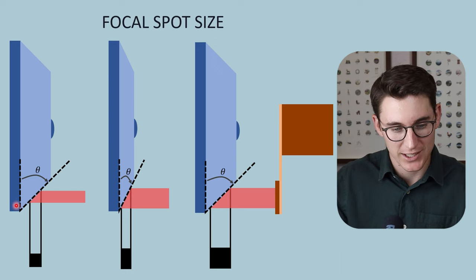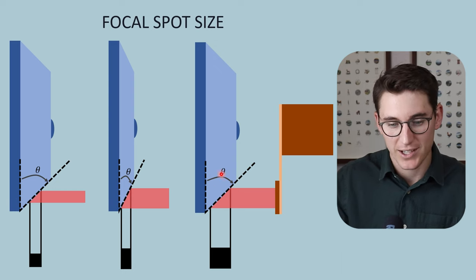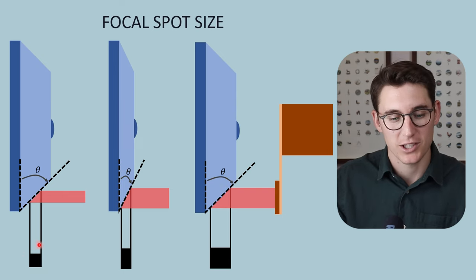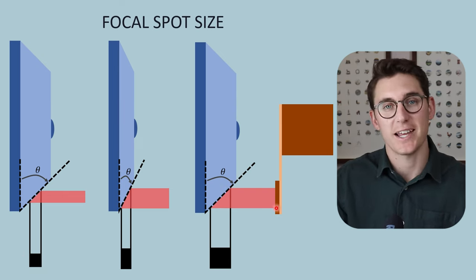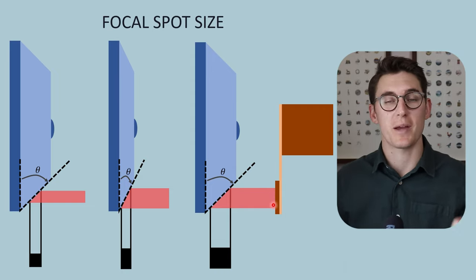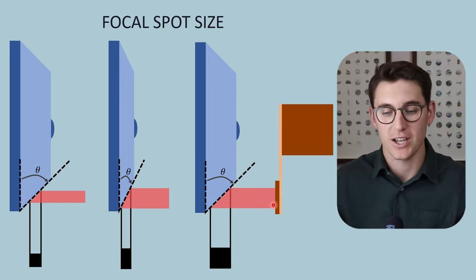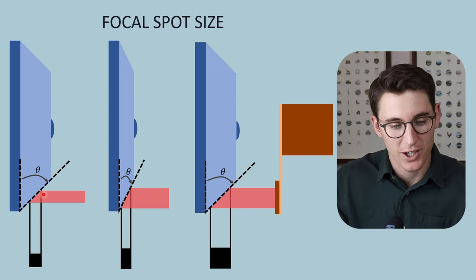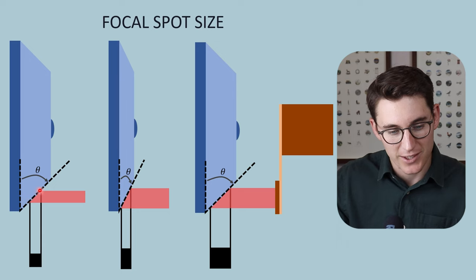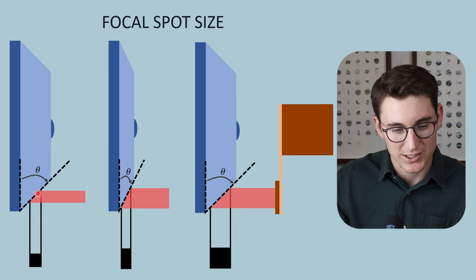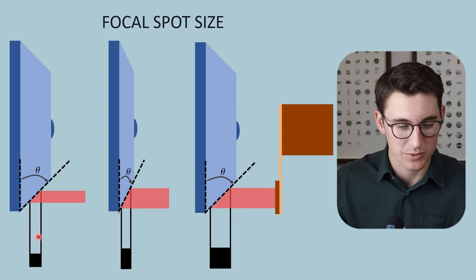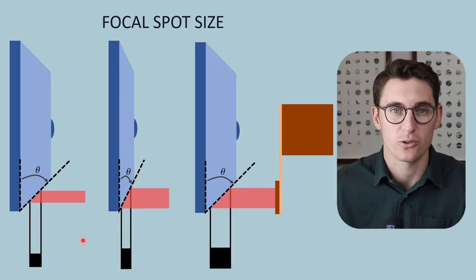The second way to narrow the effective focal spot: here the anode angle on the left is the same as on the right, but we have a much narrower effective focal spot. This is achieved by selecting the smaller filament on the cathode. By decreasing the height of our electron beam, we decrease the point of contact between the electron beam and the anode, decreasing our actual focal spot length. In turn, from the line focus principle, we have narrowed our effective focal spot.